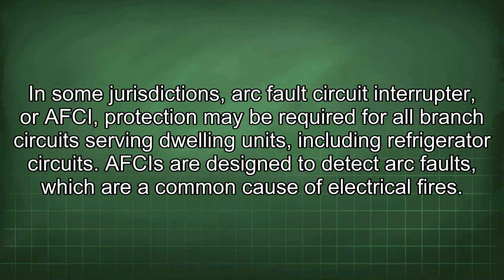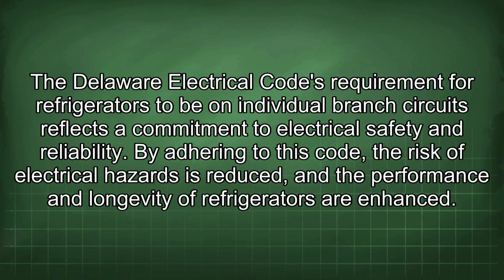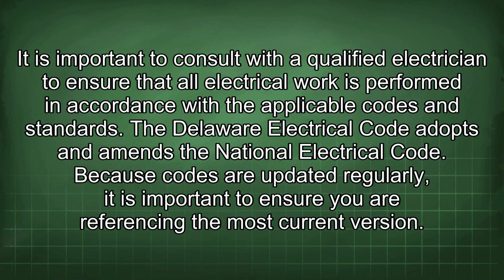In some jurisdictions, arc-fault circuit interrupter, or AFCI, protection may be required for all branch circuits serving dwelling units, including refrigerator circuits. AFCIs are designed to detect arc faults, which are a common cause of electrical fires. The Delaware Electrical Code requirement for refrigerators to be on individual branch circuits reflects a commitment to electrical safety and reliability. By adhering to this code, the risk of electrical hazards is reduced, and the performance and longevity of refrigerators are enhanced. It is important to consult with a qualified electrician to ensure that all electrical work is performed in accordance with the applicable codes and standards.